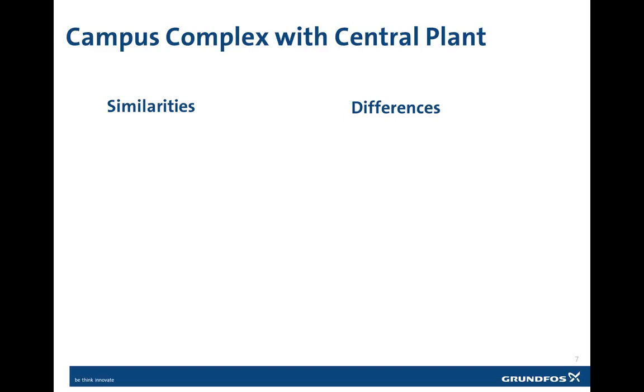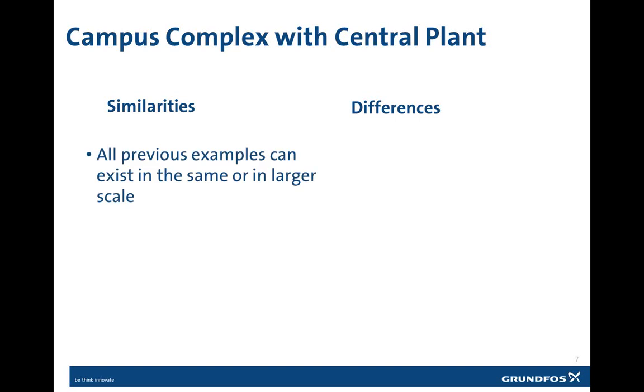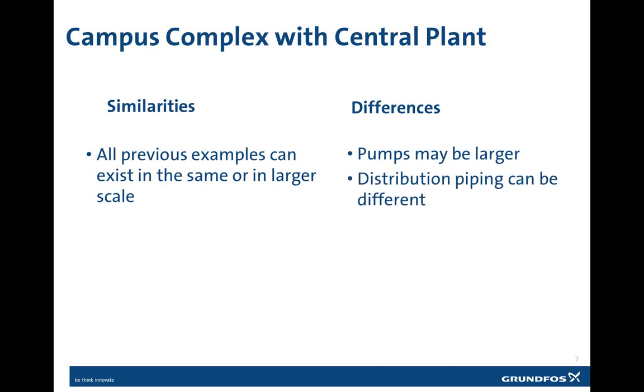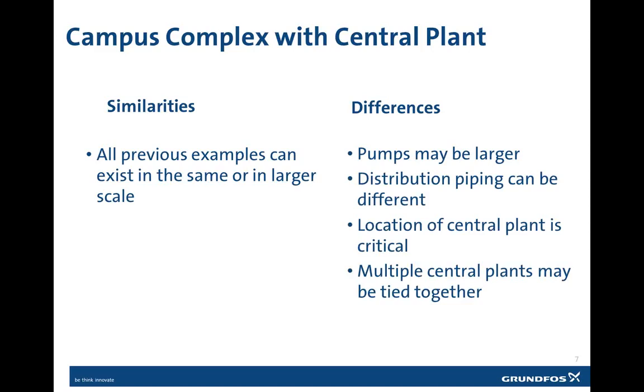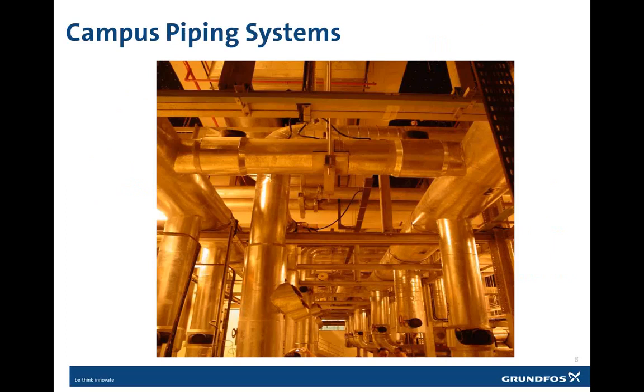So we'll look at some of the similarities and differences if we're using a campus complex with a central plant. All of the previous examples for piping for a single building could exist, but some of the differences are that the pumps could be larger. The distribution piping can be different depending on the design. As mentioned earlier, the location of the central plant is very critical to the design of the system. And multiple central plants may be tied together if needed for these types of systems. So let's explore the next level of the pump application and look at the idea of the complex central plant.